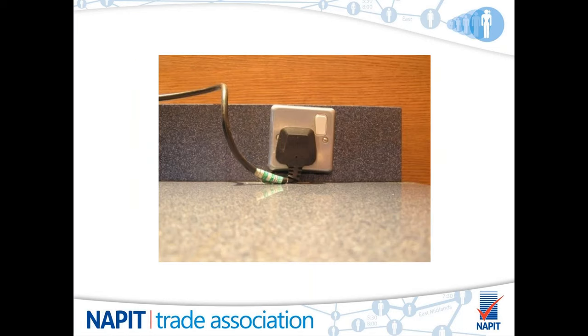This picture shows a socket outlet that has been located badly. Again, it's bad working practice because, as you can see, due to the height of the socket from the worktop, considerable stress is being put on the plug top and the flex, which again could lead to potential problems, but again, it would be a C3.